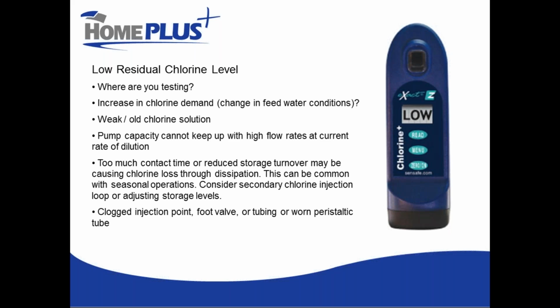So low residual could be caused by an increase in our chlorine demand. Something in our feed water conditions changed. We're pumping the same amount of chlorine in, but more of it is being used up interacting with organics or iron, etc. So our residual coming out the other end drops. We can compensate for that by improving our pretreatment, or we can up the level of chlorine we're injecting by turning our injection pump up. If you have a lot of fluctuations in feed water conditions, though, probably addressing the pretreatment will ultimately result in the most consistency in your water system.